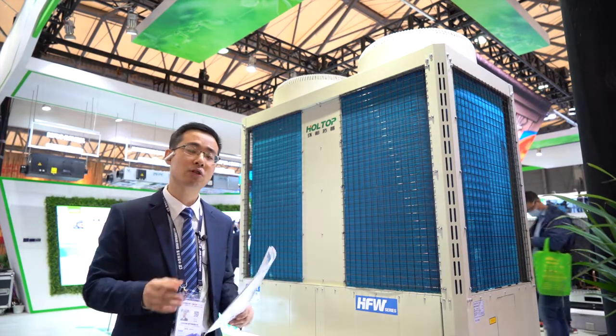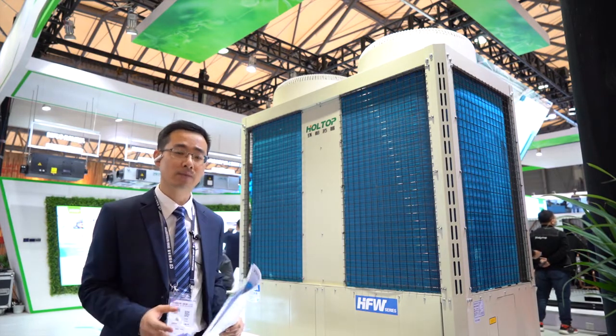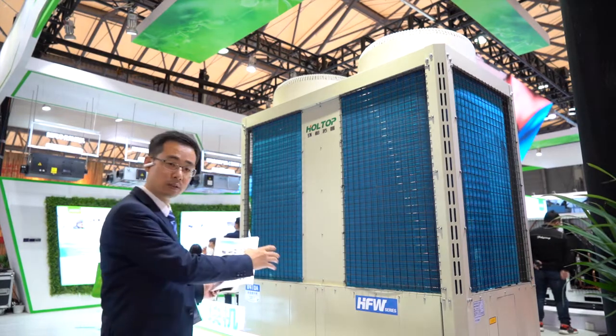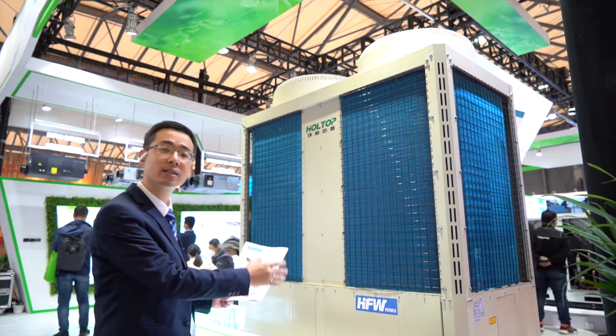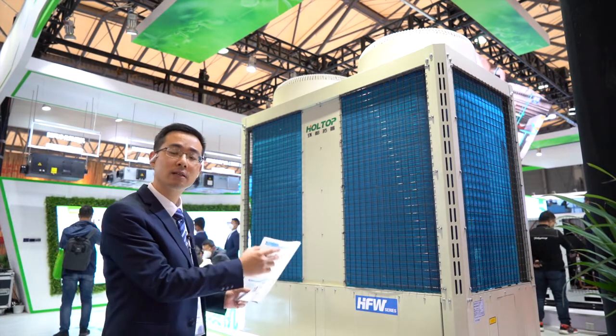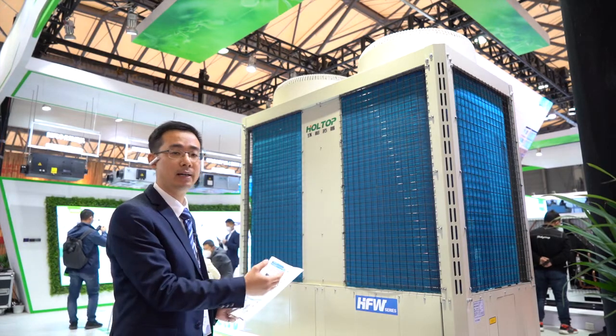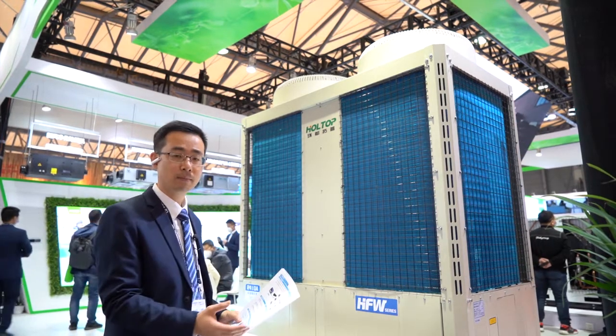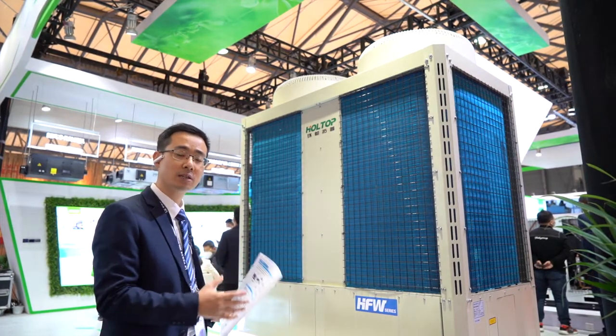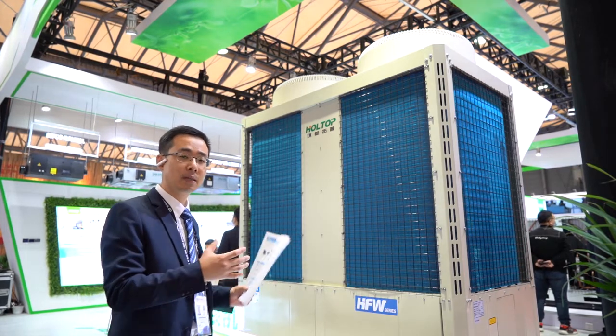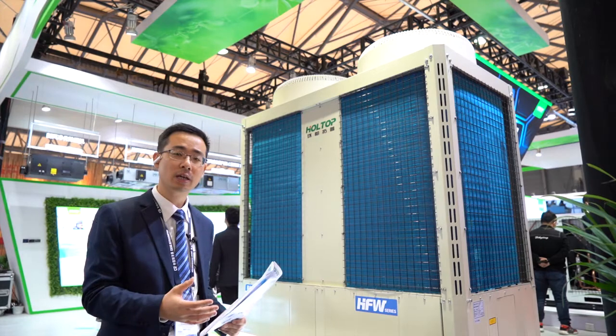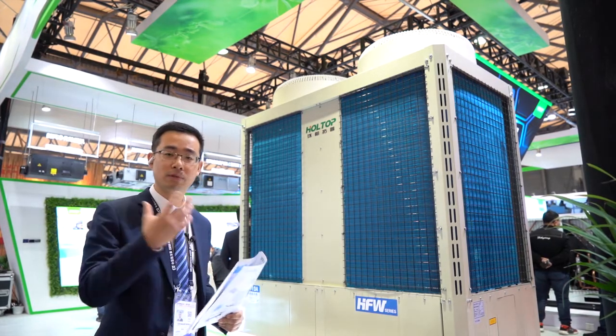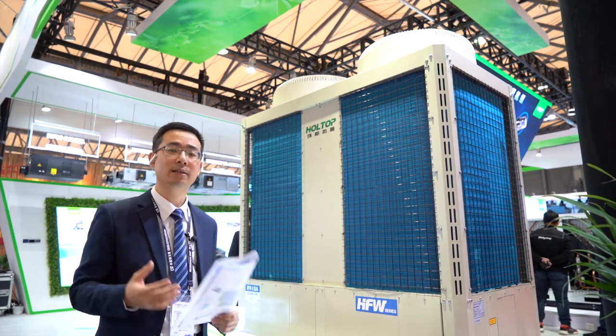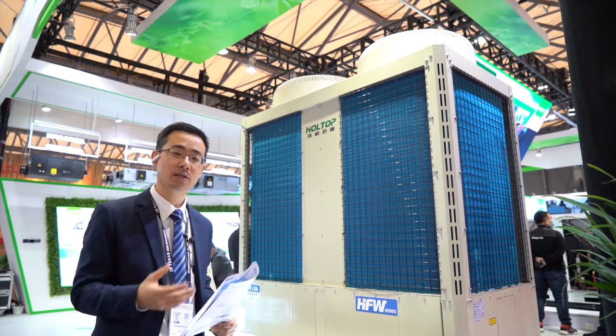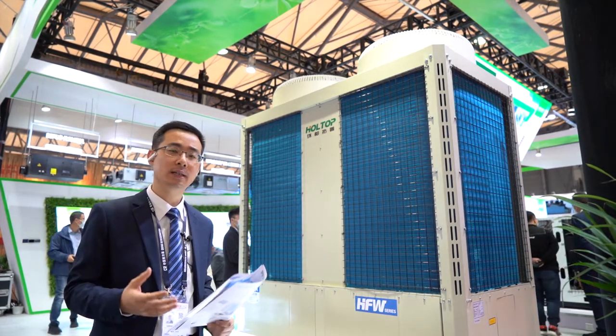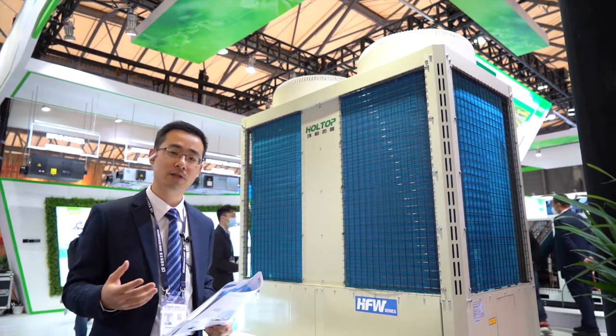And second, I'm going to talk about the control. Each chiller has a control box inside the chiller. So the customer just needs to connect the power and connect a weak current cable to the control panel, to control the chiller and the water pump. And besides that, if the project combines a lot of chillers, then the customer can have a PLC and an integrated control system to an upper computer, so that the customer can track and set the chillers from their machine room. This is also an integration for far distance control.